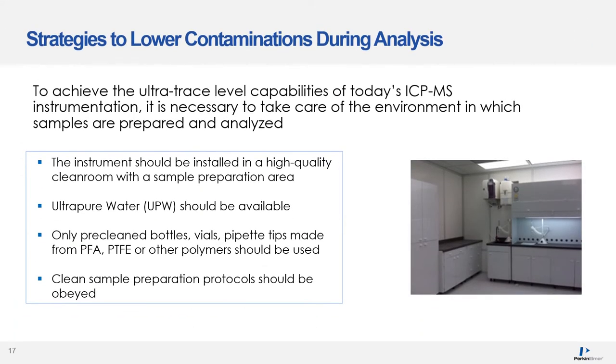To achieve the ultra-trace level capabilities of today's ICP-MS instrumentation, it is necessary to take care of the environment in which samples are prepared and analyzed. The instrument should be installed in a high-quality clean room with an extra-clean sample preparation area. Ultrapure water should be available. Only pre-cleaned bottles, vials, and pipette tips made from PFA, PTFE, or other polymers should be used, and clean sample preparation protocols should be obeyed.